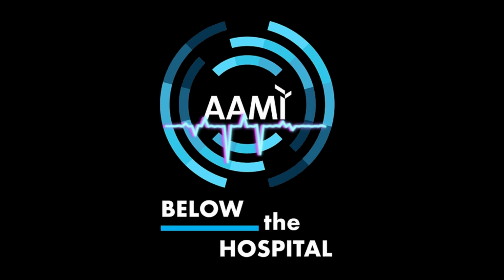At that point, we went to FDA and we spent 2 years negotiating with FDA on a testing and validation protocol specifically for duodenoscopes. Pardon me if I geek out for a minute, but when you're validating a sterilization claim on a duodenoscope, the method is to put 1 million spores, 1 million of the most resistant spores, in the least accessible part of the instrument. So in the case of an endoscope, it's right in the middle of the longest, narrowest lumen.